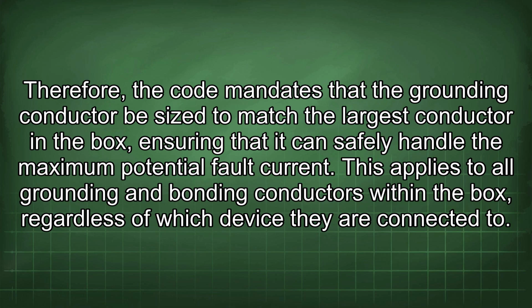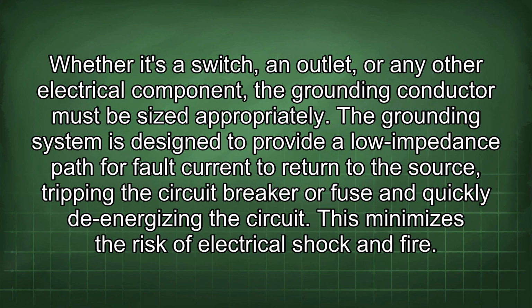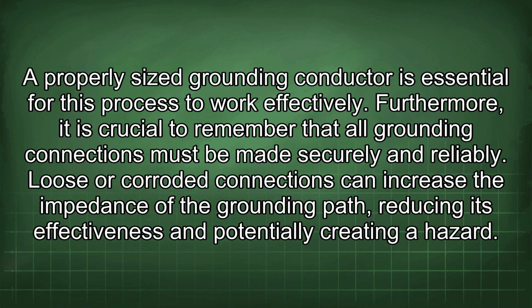This applies to all grounding and bonding conductors within the box, regardless of which device they are connected to. Whether it's a switch, an outlet, or any other electrical component, the grounding conductor must be sized appropriately. The grounding system is designed to provide a low impedance path for fault current to return to the source, tripping the circuit breaker or fuse and quickly de-energizing the circuit. This minimizes the risk of electrical shock and fire. A properly sized grounding conductor is essential for this process to work effectively.